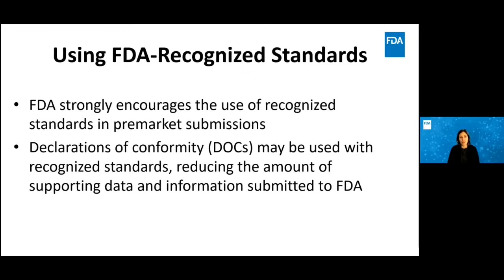That said, the use of consensus standards is voluntary. FDA strongly recommends it for all the reasons we just talked about, but their use by a manufacturer is voluntary unless a standard is incorporated by reference into a regulation. And that's a pretty rare thing for a medical device. If a manufacturer wishes to demonstrate conformity to expectations in other ways, that is their prerogative. They just will need to justify their alternative approach. Now, standards may be cited in any type of submission, such as a PMA or 510K. And as mentioned previously, if a standard is recognized by FDA, a declaration of conformity may be used. But general use of a standard is also an option. Just keep in mind that additional documentation will be needed. And we'll talk more about general use of standards in a moment.